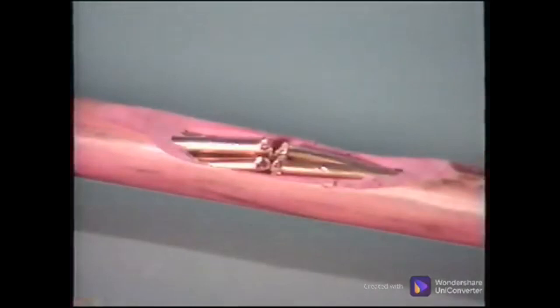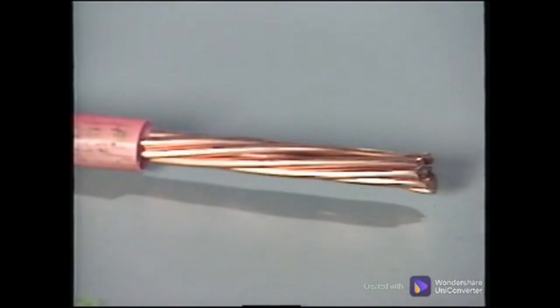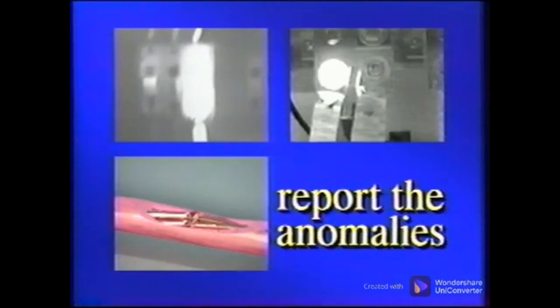Stranded wires or cables can have a break in some of the strands, which forces the load to be carried on the remaining strands. When this occurs, the good strands are usually forced to carry too much current and cause excessive heat. The broken strands will be much cooler, and the thermal image will appear as barber pole striping or candy striping. Loose connections, overloading, and broken strands each have their own unique characteristics, which can be distinguished in a thermography image. Whether the temperature is within tolerance or even measured may not be of any concern here. The fact that there is an anomaly requires action.